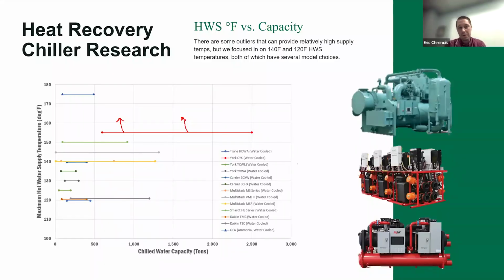And then you even have some natural refrigerants in the mix, ammonia for example, like GEA. They have two options, piston and screw machines, that can take you up to 180 degrees or so and up to about the 500-ton range. So we're continuing to develop our knowledge on this and continuing to document what's available out there. And it's changing. I don't want to say quite day by day, but it's almost day by day. We had, who was it, Bill, that came in? It was the Multistack guys. Some other companies do custom fabricated screw-type machines. I was looking at them at the University at Albany as an option, and they're doing the same thing, where you get 170-plus degree hot water and 42-degree chilled water. So continuing to evolve is the big takeaway.